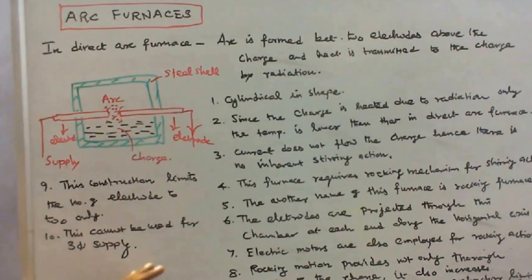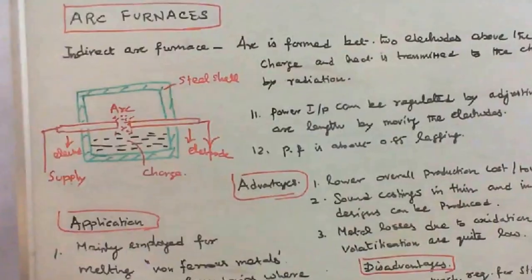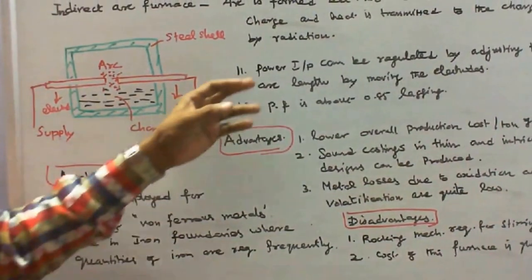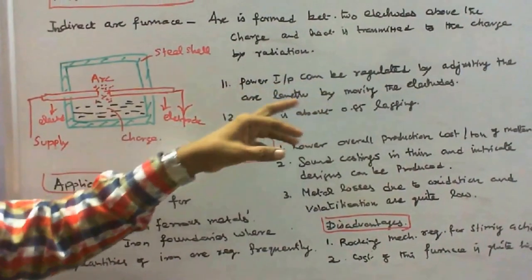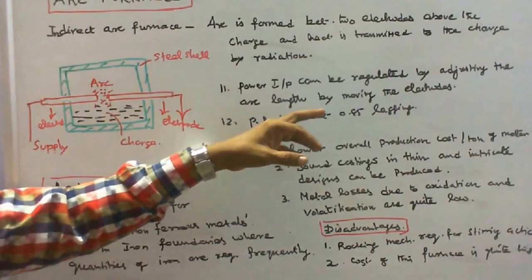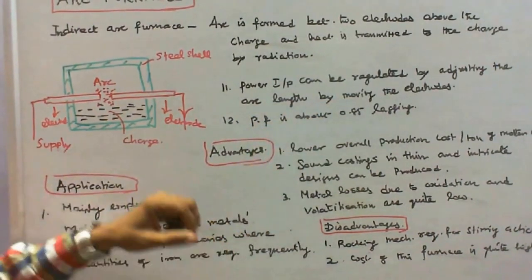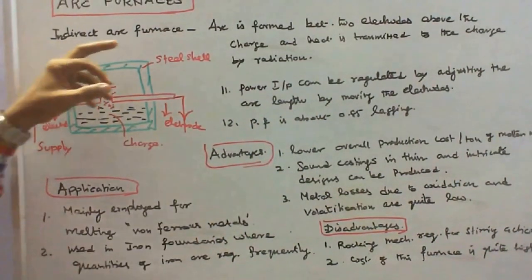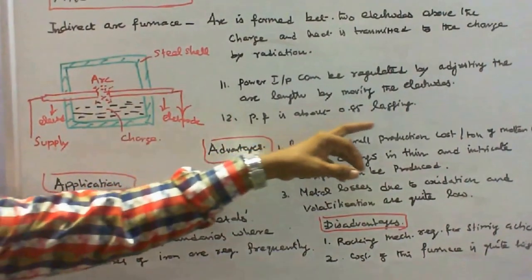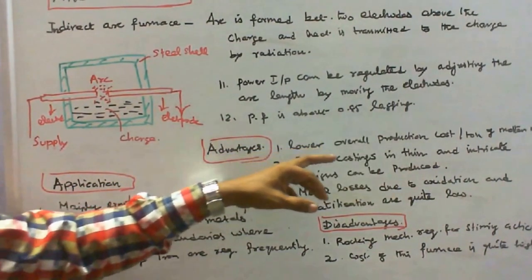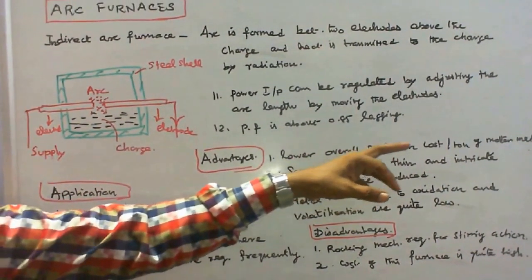This cannot be used for three-phase supply. Power input can be regulated by adjusting the arc length by moving the electrodes. The power factor of indirect arc furnace is about 0.85 lagging.